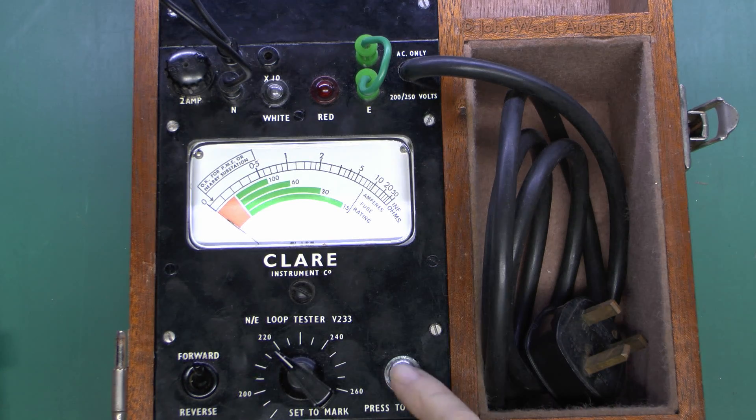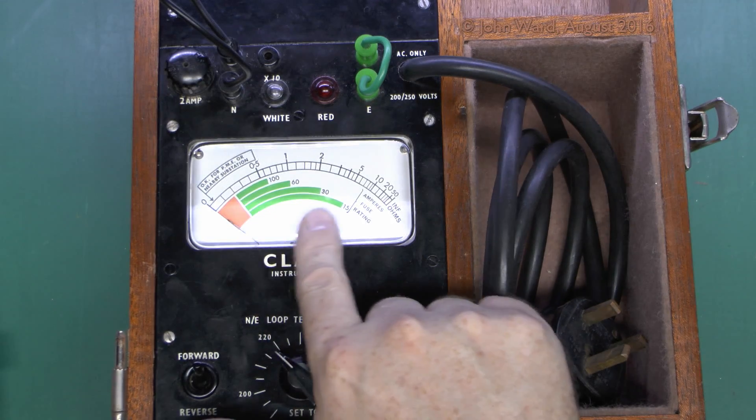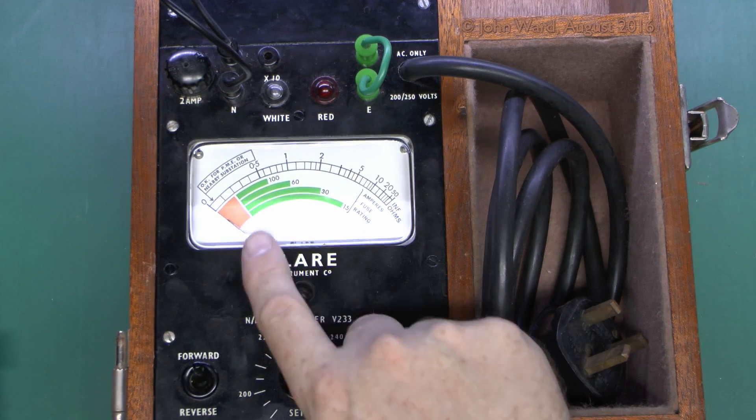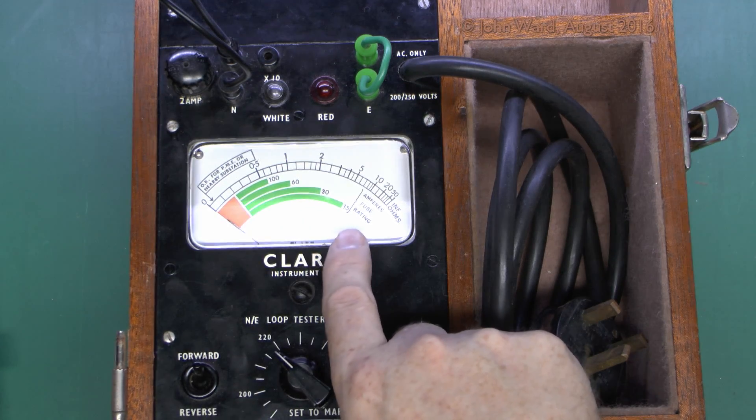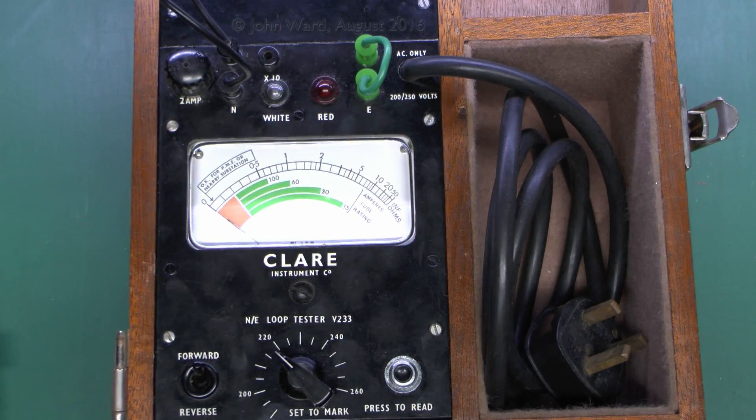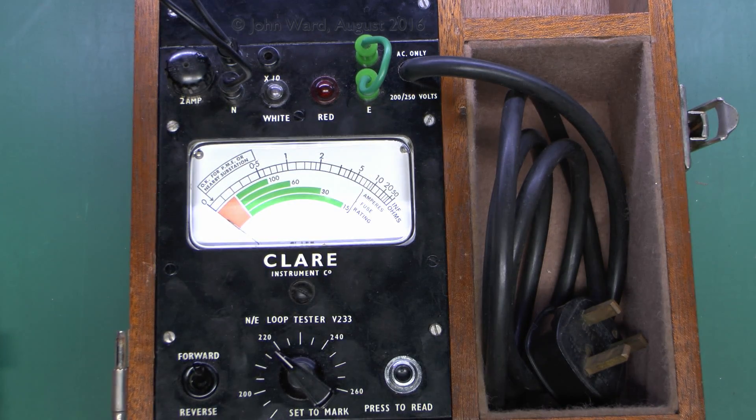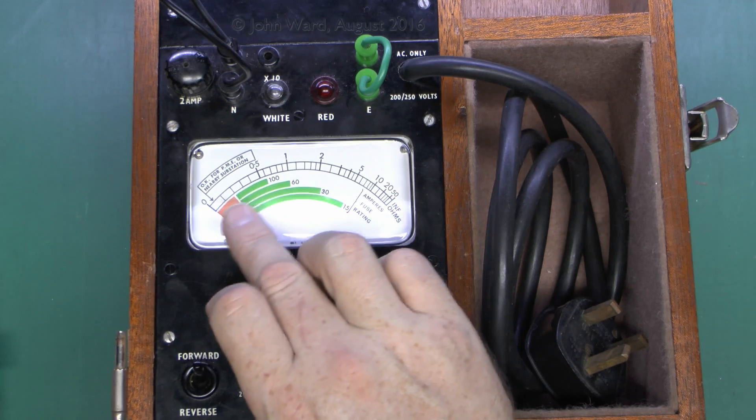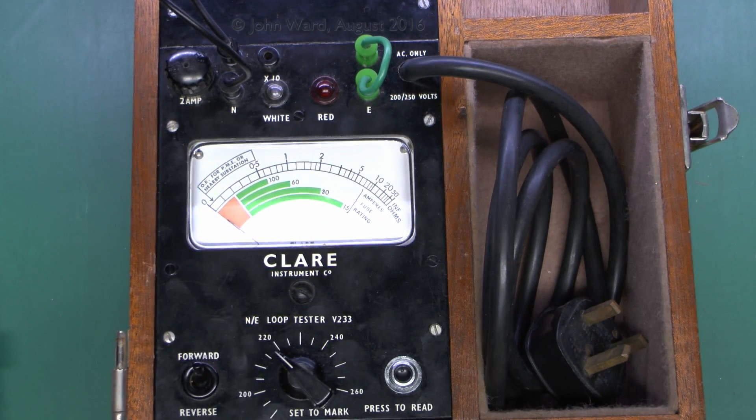And other than that then it's just a question of pressing the test or press to read button. And then the pointer will move from here down to some point along this scale which will give you the actual impedance of the neutral earth loop. The green segments here are intended to show whether it's in the correct kind of impedance range for these ratings of fuses, so you've got 15 amps, 30, 60 and 100. So depending on which value of fuse you were using on the particular circuit, then it would expect to see within the green band as appropriate. As we saw in the previous video, the higher the rating of the fuse or protective device, the lower the impedance needs to be, so that in the event of a fault the current that flows is sufficient to cause the fuse to blow within the required time.